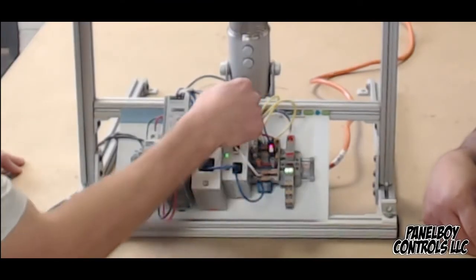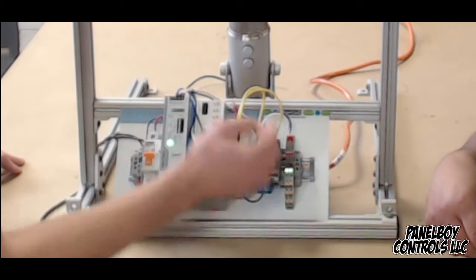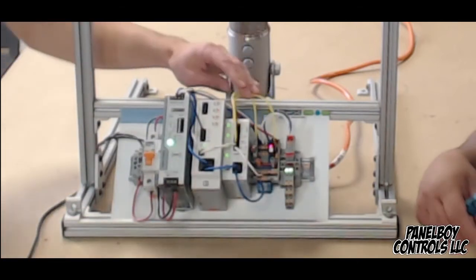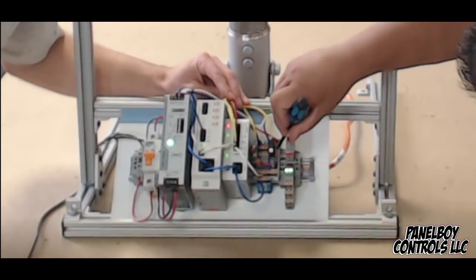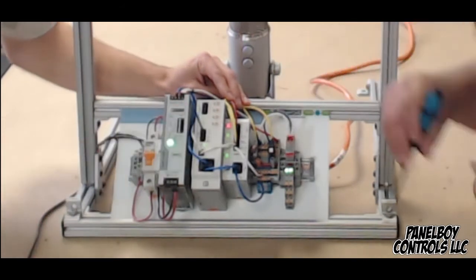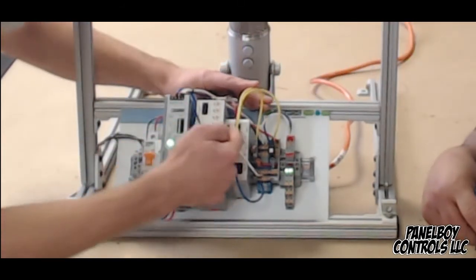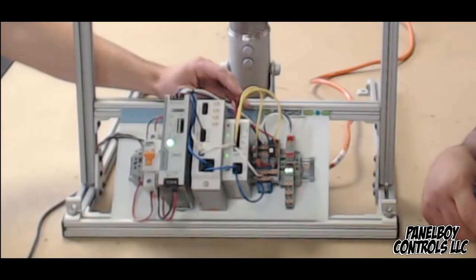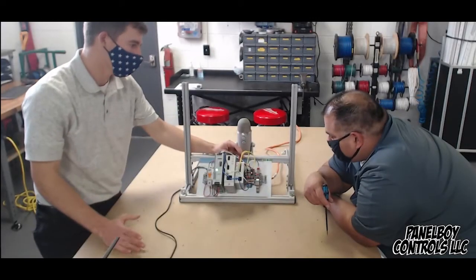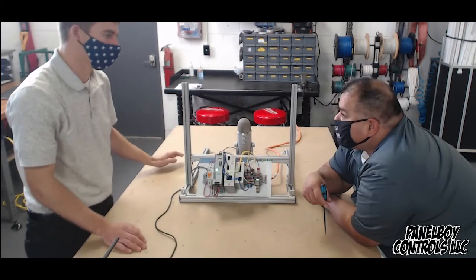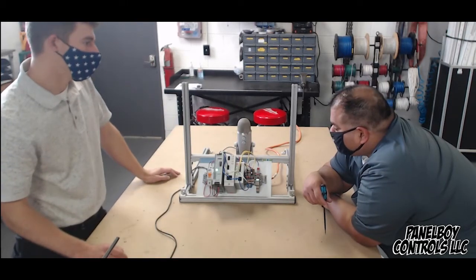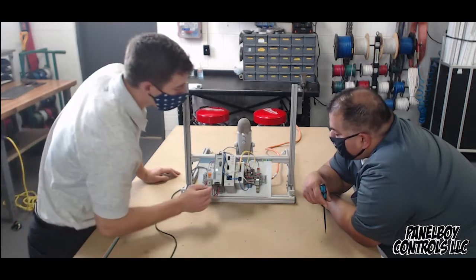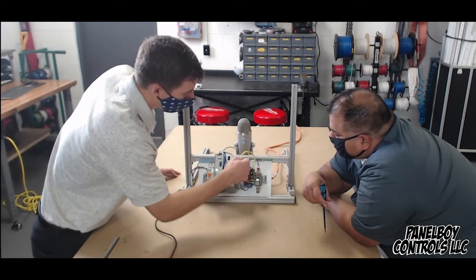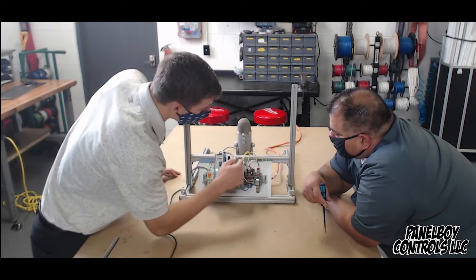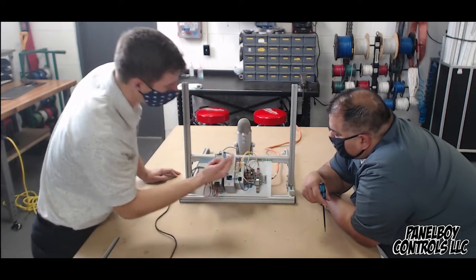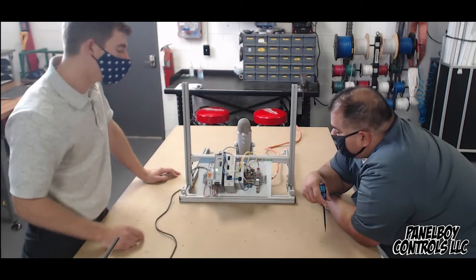Now that this load is set to 3 amps, we can trip it by pressing that knife disconnect closed. You'll notice the light went out right away, indicating it tripped both locally, because it turned red, and remotely as well. Typically that's tied to something like a PLC, some type of alarm bit that lets you know something's not right. To reset it, I can either press the reset button or turn it on locally - notice it didn't turn because it's still shorted.